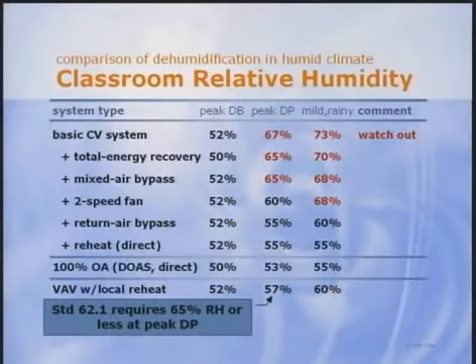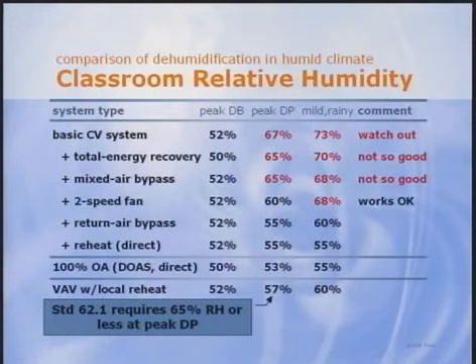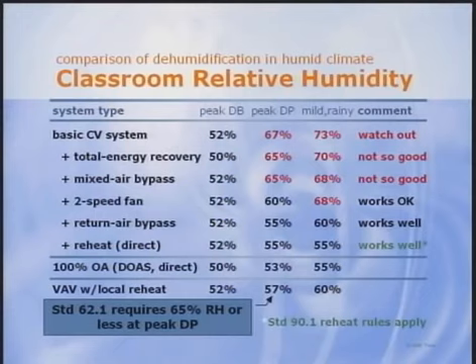Here's a comparison of our results for a classroom in a humid climate, like New Orleans, at different load conditions. As we just saw, constant volume single zone systems often don't control RH at design dew point, much less on rainy days. Neither energy recovery nor mixed air bypass configurations control humidity very well. Two-speed fans can meet ASHRAE 62 in this example, and return air bypass works well, and it uses no direct humidity control, so standard 90.1 rules don't apply. Supply air reheat with direct humidistatic control works well too, but here standard 90.1 rules do apply, so be careful.